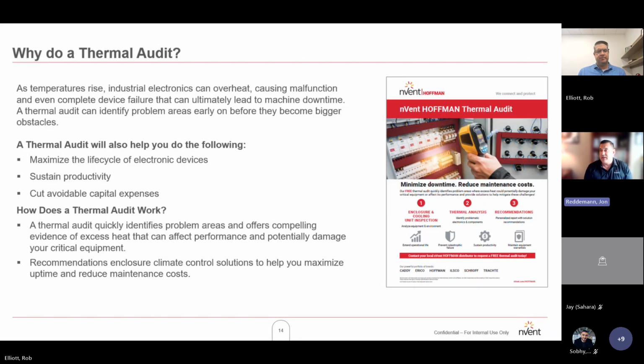Anytime a new panel has been installed would also be a good time to do an audit. Don't always assume that because it's a new machine, the calculations are done correctly. We see a lot of new installations where, I hate to say this, costs were cut or there was a miscommunication in the application. So maybe the proper temperature profiles were not used during the initial design phase. But it's good to do an audit, especially if you're experiencing potential premature failures. If the enclosure temperature or heat load is managed correctly, you should see 10 years out of your components. If we're seeing premature failures, that is a prime candidate for an audit.